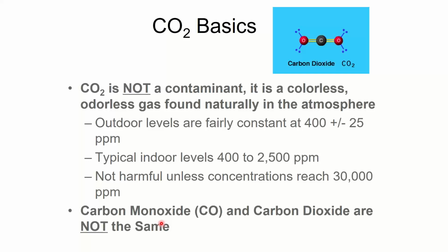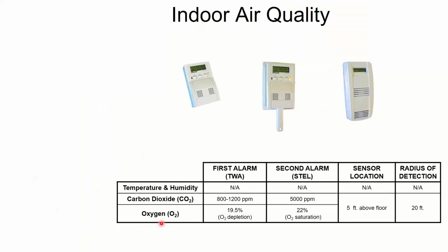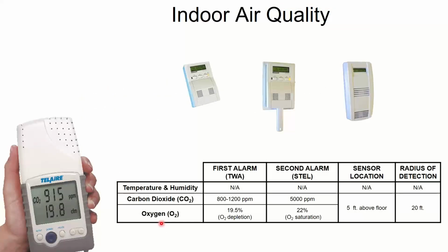So I can essentially use CO2 as a surrogate to digitally count the people in there and decide if I need more or less ventilation. Normal levels should be between 800 and 1200 parts per million. Now, if you have an economizer on your unit and you're in economizer mode, the CO2 level is going to go down because you're using all that outside air for free cooling. But when things are in normal operation, you definitely shouldn't be above 1200. Usually the target is 700 parts per million above the outdoor ambient level.